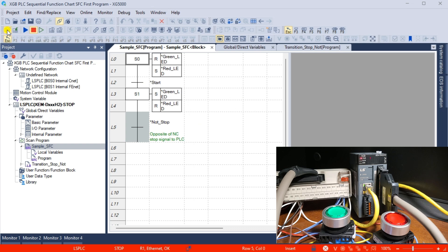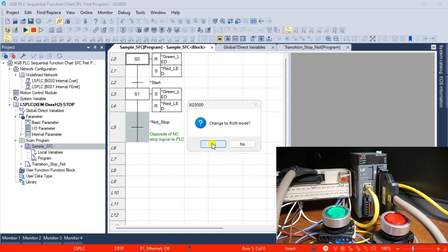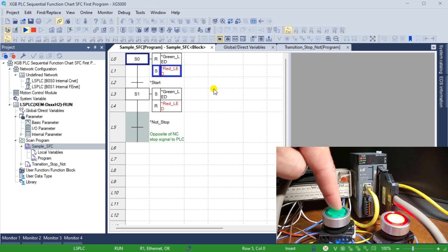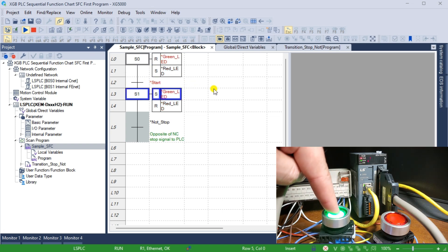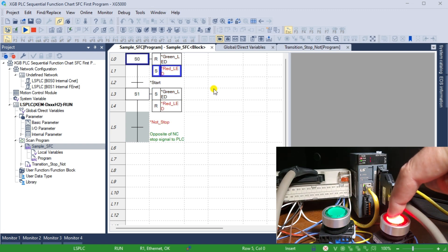The PLC connection will then be stopped, shown as the blue bar at the bottom of the XG5000 programming software. Select Connect from the main menu Online to reconnect to the PLC. Select the monitor icon on the main menu. This will show the status of our program as it executes in the PLC. Select the run icon on the main menu and select Yes to verify that we want to change to run mode. The bar at the bottom is now green, indicating we are communicating with the PLC and it is running our code. Operate the green and red pushbuttons to verify the program's operation. The SFC program illustrates the basic control logic for our start-stop circuit.